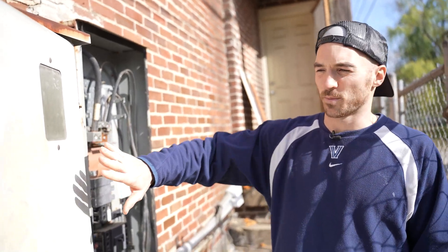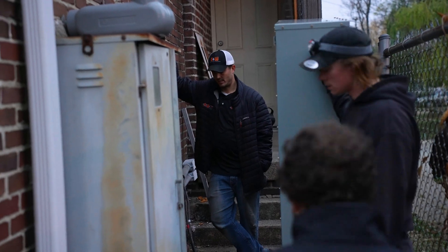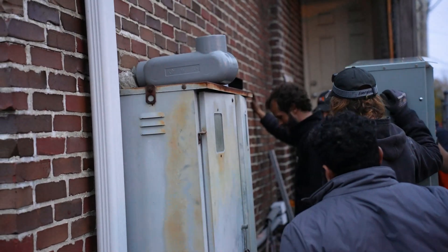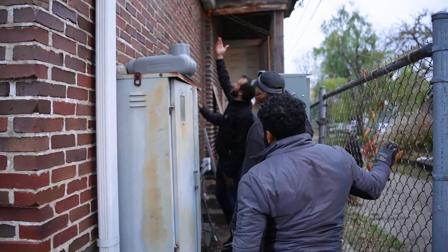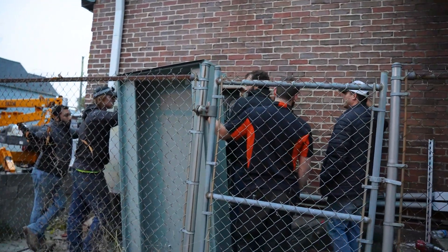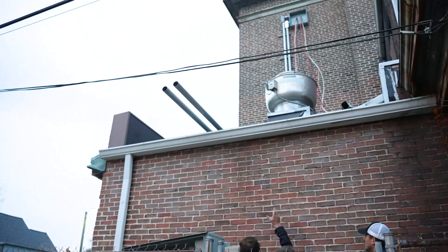This is our currently existing equipment — this is the CT cabinet that the utility uses to actually monitor and meter the electrical draw. Here is the still-functioning electrical panel. Ours is not replacing it, just going alongside it right here. What if we split the difference and didn't bring it down all the way? We could raise it up a little bit, honor that 6'7" off of this measurement, and space the conduit out — we'd still need to remove the gutter and only pull it out 3 inches total. You would need a spacer between the panel and the brick to secure the vertical pipes.